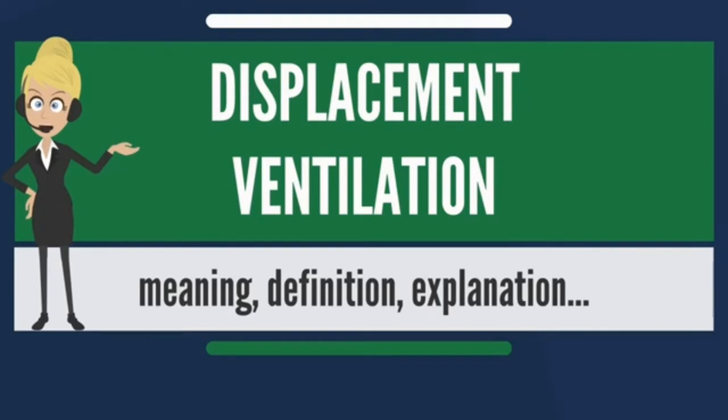A typical displacement ventilation system, such as one in an office space, supplies conditioned cold air from an air handling unit (AHU) through a low induction air diffuser. Diffuser types vary by applications. Diffusers can be located against a wall, wall-mounted, at the corner of a room, corner-mounted, or above the floor but not against a wall, freestanding.